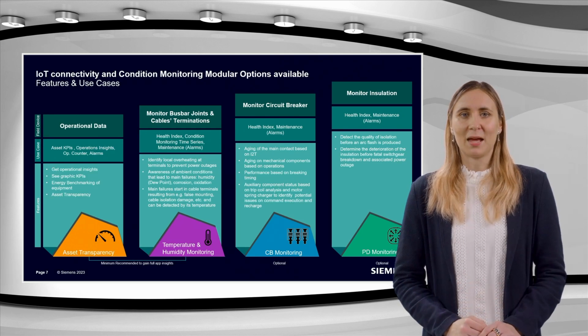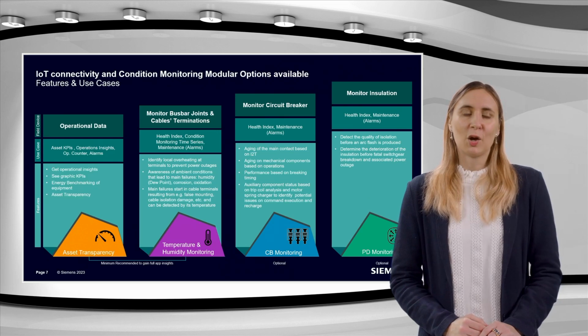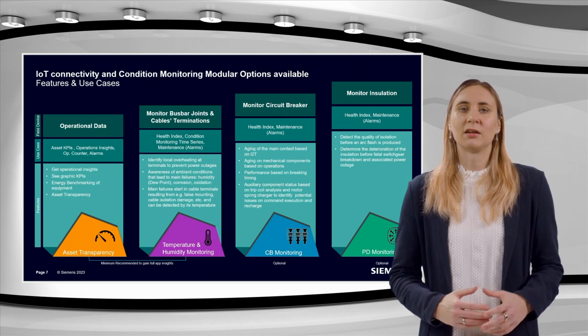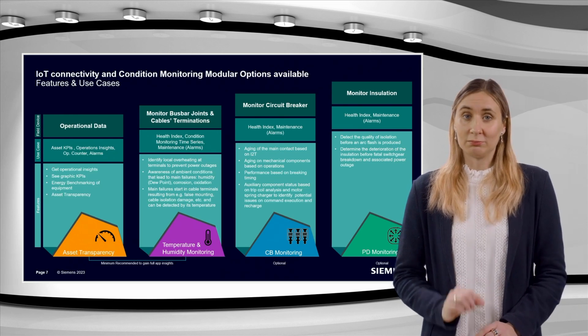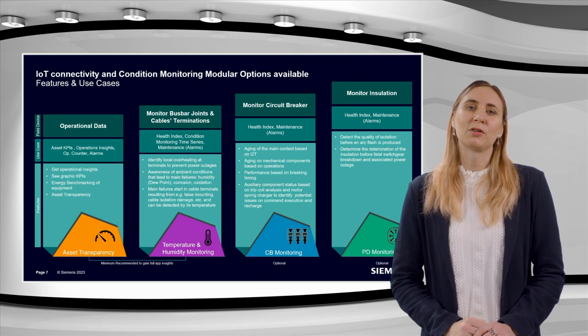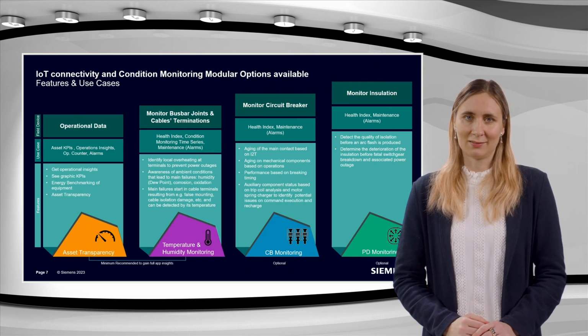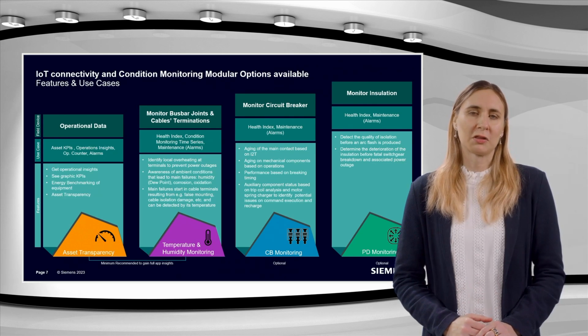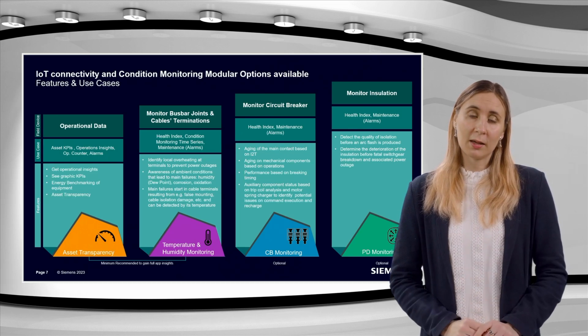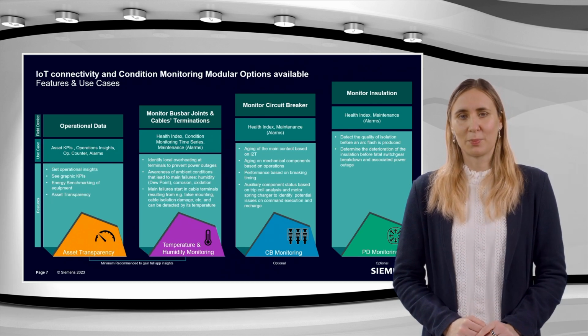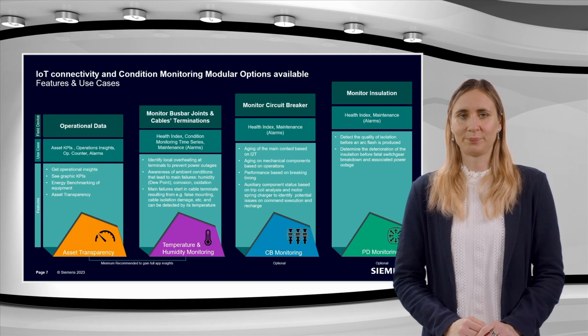Third is partial discharge monitoring, which helps in the detection of started insulation faults - gradual, creeping faults which, if left undetected, can lead to a shutdown. Partial discharge measurement can detect faulty components, for example in the medium voltage connections, insulators, bushings, or voltage converters.